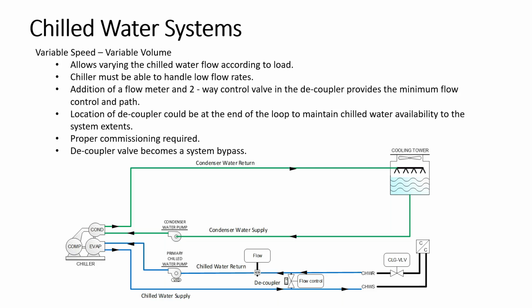Sometimes we can put this decoupler at the end. I've seen these on the end of the loop, where you push water all the way out to the end and it bypasses all the way back. That way you ensure that you keep flow all the way through the system, all the way to the end. So the location of the decoupler is not critical when it's a primary only system.